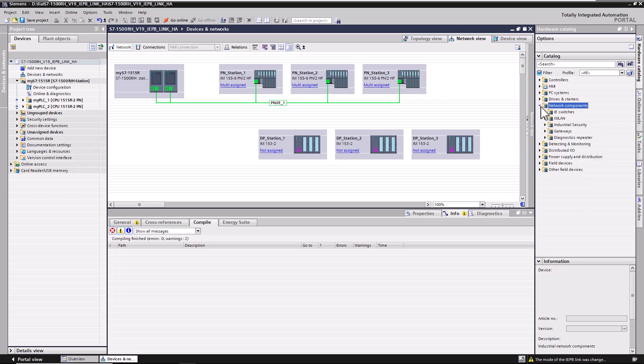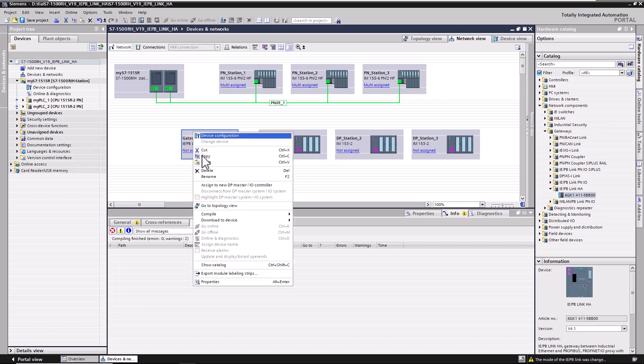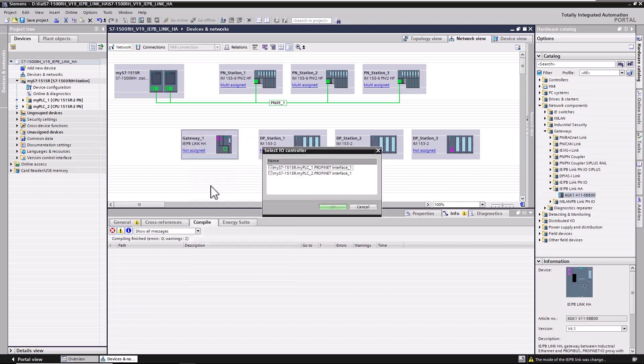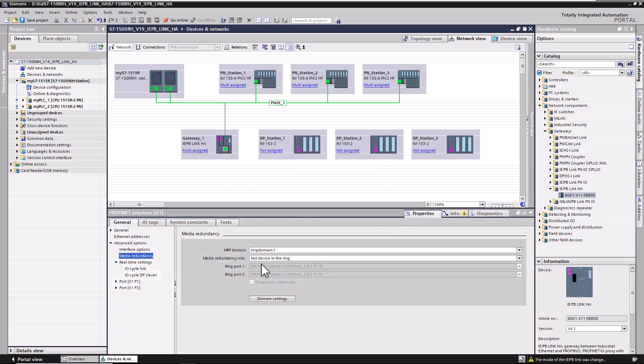Let us show you a quick demo. A project is already prepared. The DP devices are configured. First, add the gateway into the hardware configuration. The gateway is assigned to the redundant system and configured as MRP client.